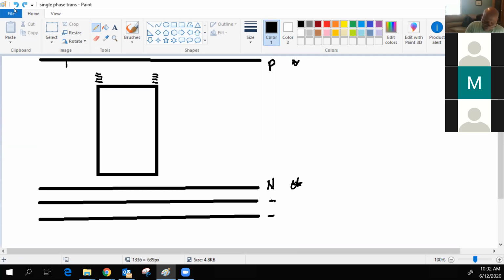Okay, so we come in at the primary. On the primary side, we'll have a fuse on it. We'll come into the top bushing on the left-hand side. The windings go through the transformer, through the core, and remember, it does not touch the core. That's a laminated core, so nothing is actually touching, it's just going to be induced. This will go down and tie back to the neutral or ground. Everybody good with that so far?